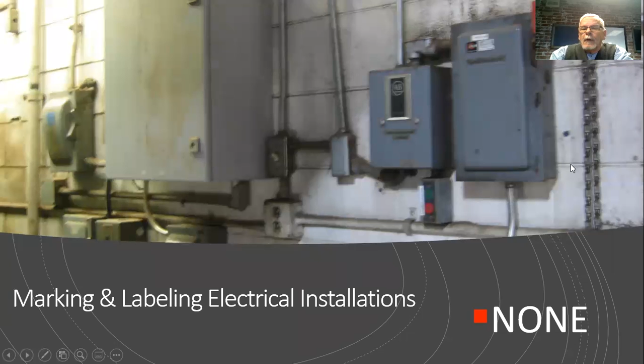This is 101: all electrical installations, all electrical cabinets, all electrical switches at a bare minimum have to be marked with their voltage on the outside. You go through a lot of places and they don't have it. We have 4 different examples here, none of which have the voltage marked on them, so you could say this facility faces 4 separate actions.